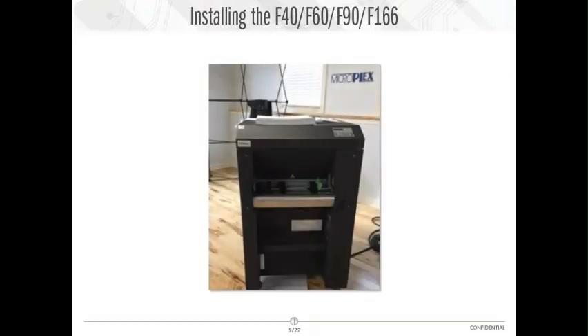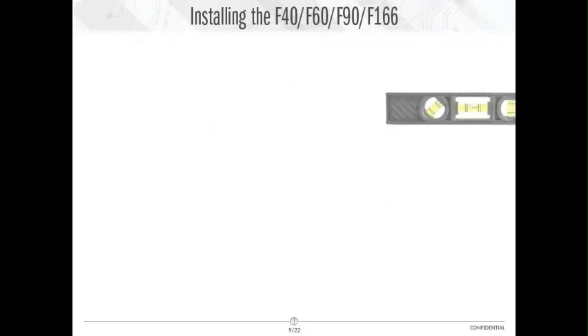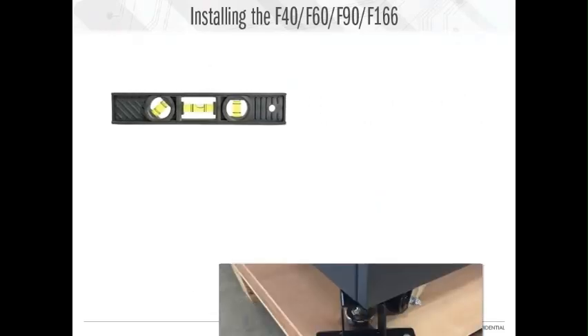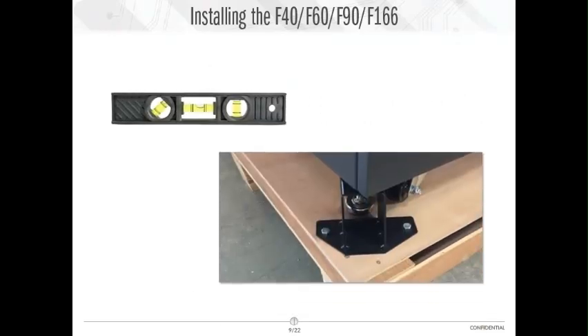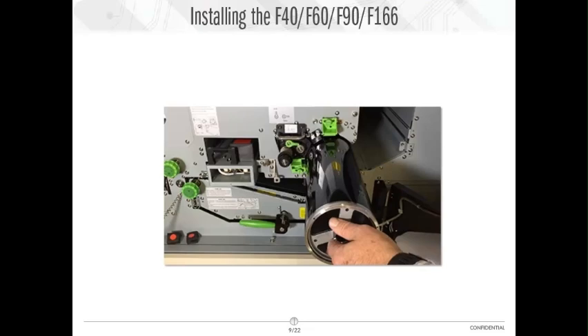Now that the printer is unpacked and set in position, use a level and level the printer using the legs on each of the corners of the printer. This procedure is not outlined in the manual. Next, set the OPC drum using the instructions in the installation section of the maintenance manual.